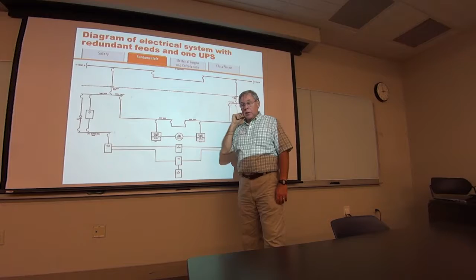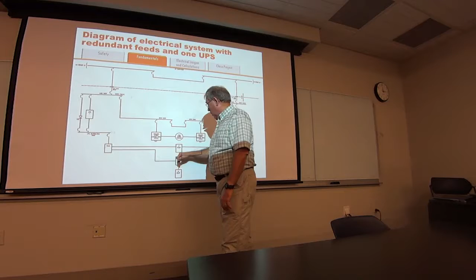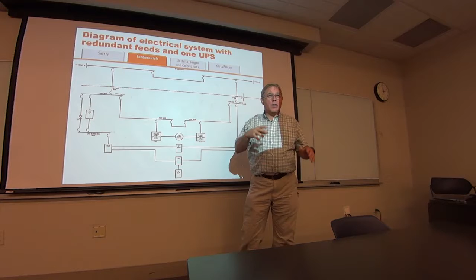So now, I added a cold water storage tank here. And the reason I did that is because I could ride through power quality events where the voltage goes down, comes back up, and keep my loads going. This side over here will see the dip, but it won't affect it because I've got the UPS riding through it. But chiller plants, pumps, chillers, they have VFDs in front of them, variable frequency drives.